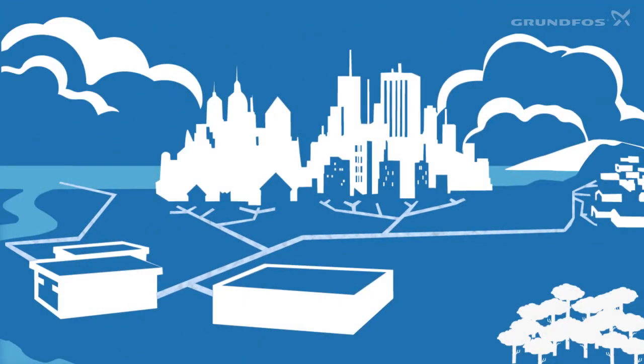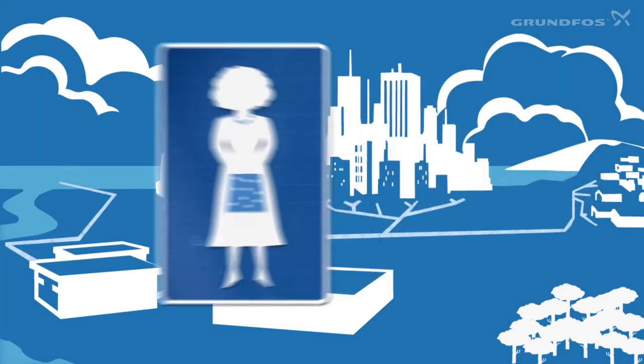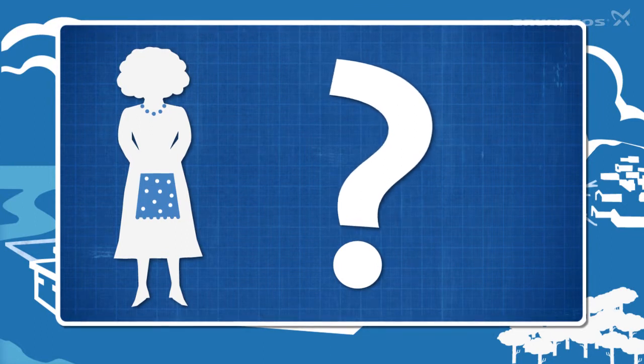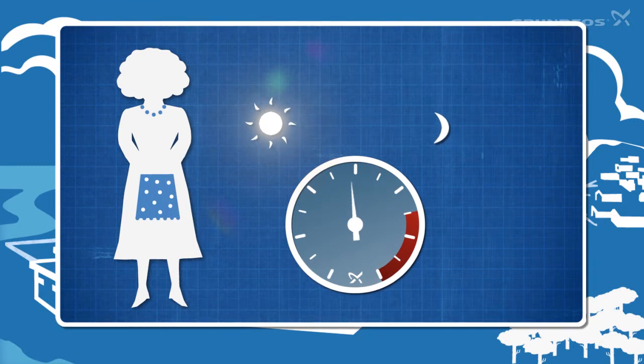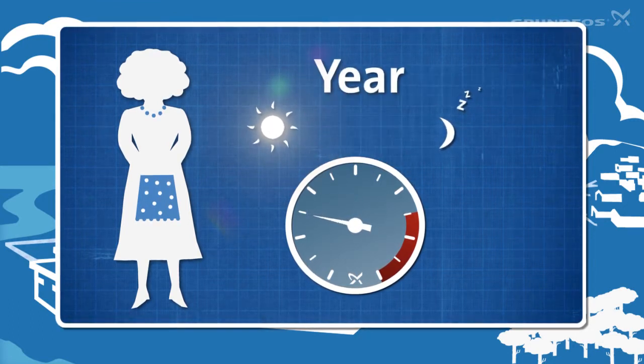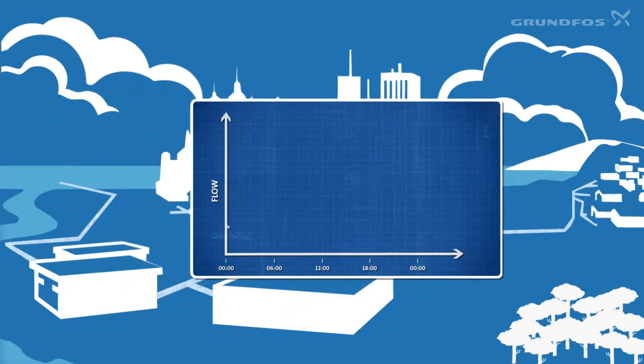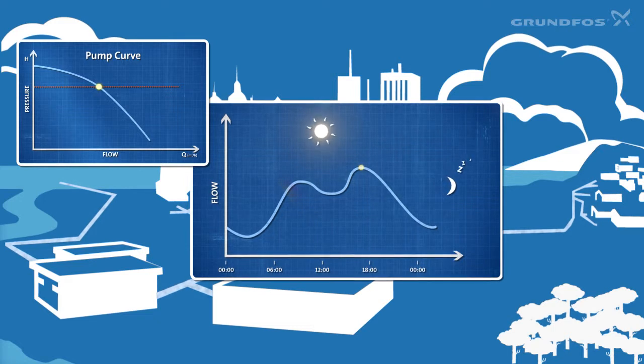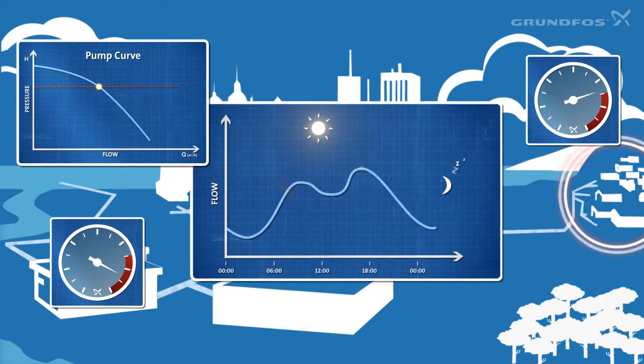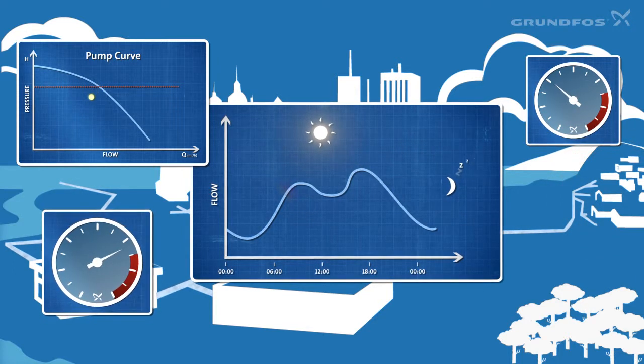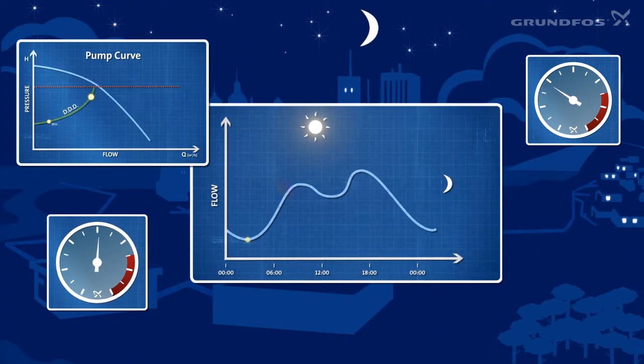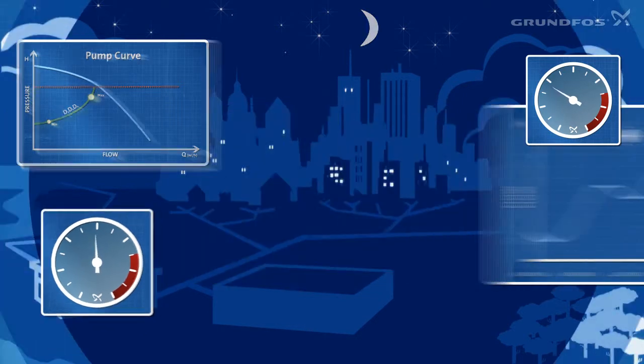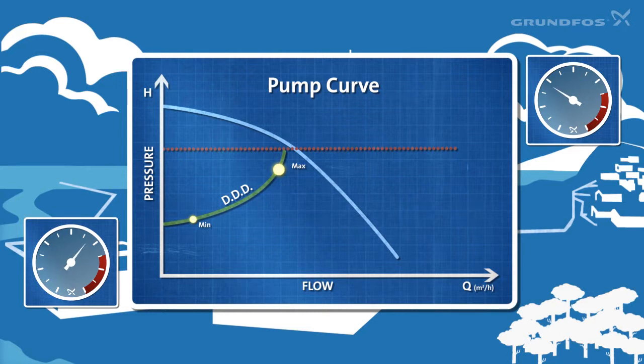We say that a demand-driven distribution system keeps the water pressure at Mrs. Smith as high as she needs it. We don't need to know for sure all the time — we just need a pretty accurate idea about the variations in demand over the course of a day, a week, even a year. For example, if maximum demand occurs around 5:30 pm, we check the pressure at Mrs. Smith and can turn down the pump if it's too high. The minimum demand at 3:30 in the morning also informs pump adjustment, while always maintaining the minimum pressure required to avoid contamination through leaks into the pipes.